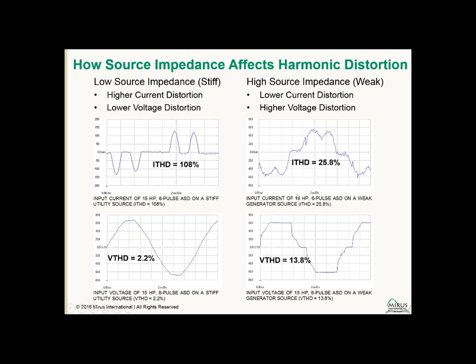But if we take that same 15 horsepower drive, and now supply it from a weak source, a generator source, with typically high subtransient reactance, then that added impedance is going to lower the current distortion. The drive is going to draw current that's broadened somewhat, so there are not as sharp pulses, and this current wave shape contains fewer harmonics. So now we've got current distortion of less than 26%. But at that lower current distortion, we have much higher voltage distortion because of the added impedance of the source. So the voltage distortion is almost 14%.